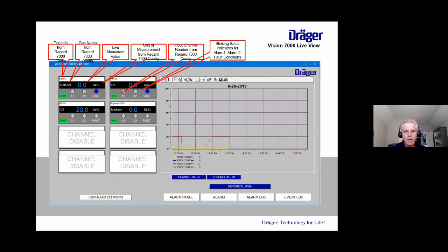So I mentioned Vision 7000 software, and this is a screenshot of what it looks like. You can set one of these screens up to have up to 32 inputs on one screen. Of course, you could go through multiple screens if you needed to. But you can see for the first point there, we have a Polytron 8700 reading hexane. So it tells you the gas type, it tells you the value, tells you what the units are, and it tells you with these little LEDs, A1, A2, and fault, if there is currently an A1, A2, or fault, or if it's green and all good. So you can do that for each of the channels. And when you order that panel PC with the Vision 7000 on there, that's part of what the guys in Houston do, is they pre-program these things to show all those different values on the Vision 7000 screen.